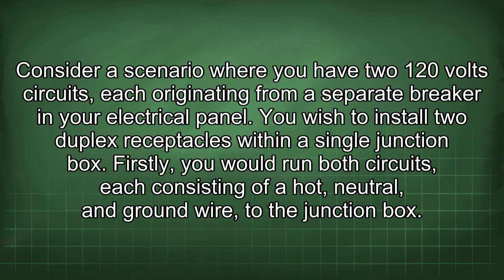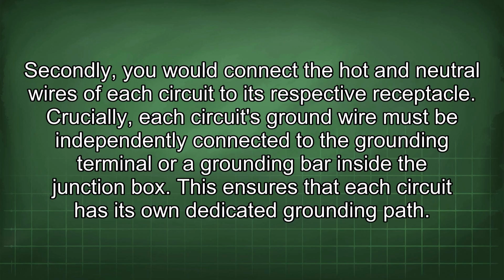shock. Consider a scenario where you have two 120-volt circuits, each originating from a separate breaker in your electrical panel. You wish to install two duplex receptacles within a single junction box. Firstly, you would run both circuits, each consisting of a hot, neutral, and ground wire, to the junction box. Secondly, you would connect the hot and neutral wires of each circuit to its respective receptacle. Crucially, each circuit's ground wire must be independently connected to the grounding terminal or a grounding bar inside the junction box. This ensures that each circuit has its own dedicated grounding path.